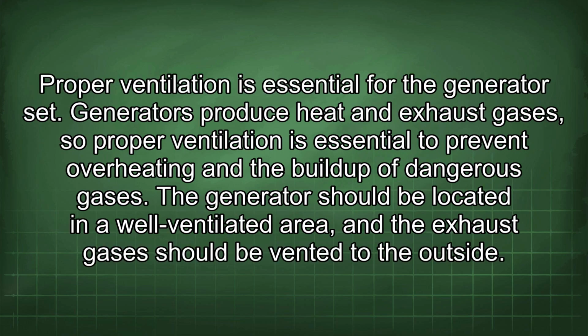Proper ventilation is essential for the generator set. Generators produce heat and exhaust gases, so proper ventilation is essential to prevent overheating and the buildup of dangerous gases. The generator should be located in a well-ventilated area, and the exhaust gases should be vented to the outside.